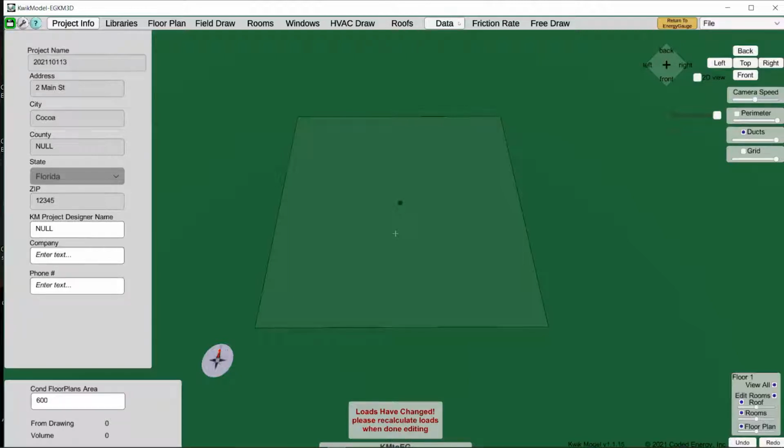A lot happens in the data tab. That's where every time you draw a room, it calculates the areas of all those surfaces. When two rooms touch each other, it knows that the walls where those rooms touch are not between conditioned and unconditioned space. So it ignores them. So every time you add a room, it changes all the geometry of the house. So your room sizes, your floor areas, your wall types, your window types, that's all going to appear under the data tab.